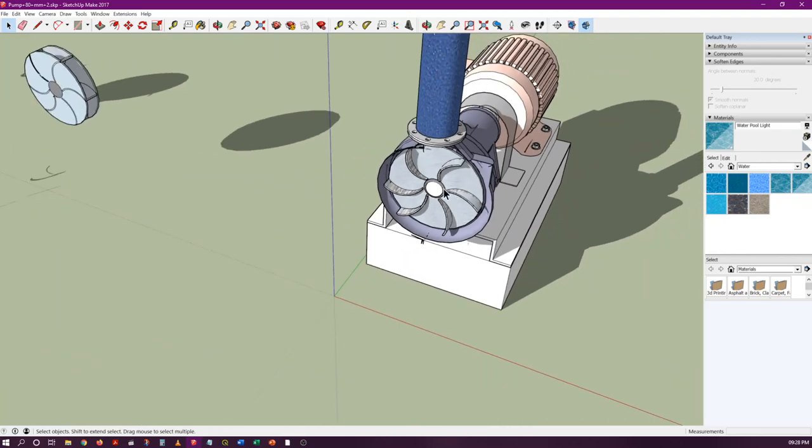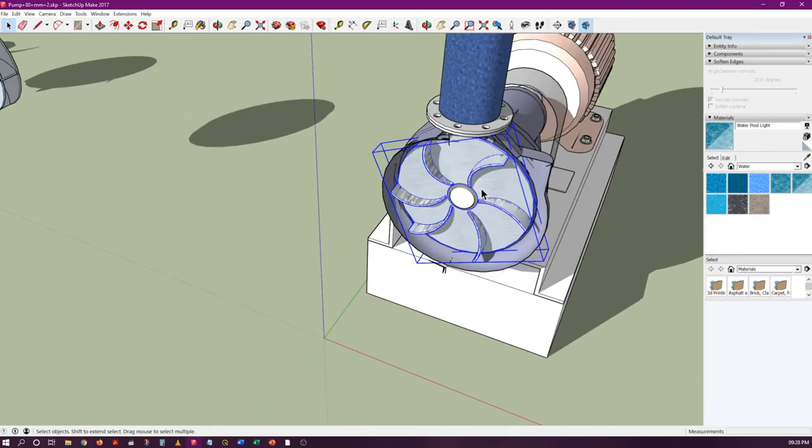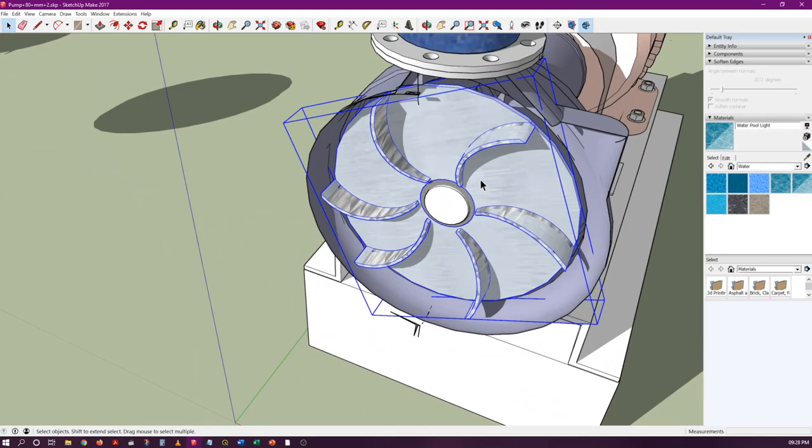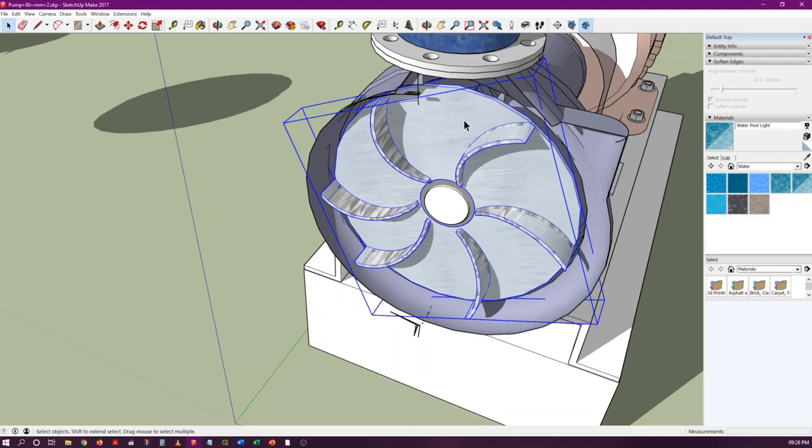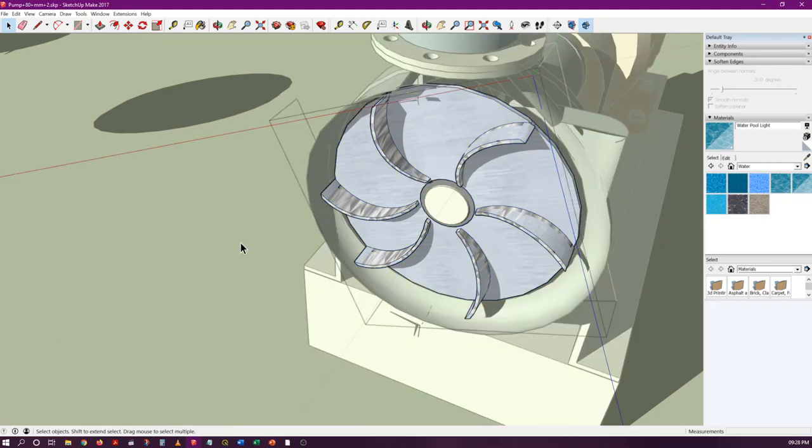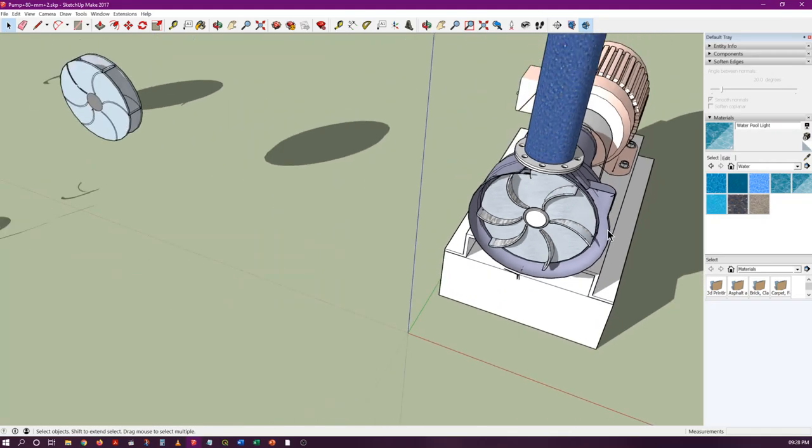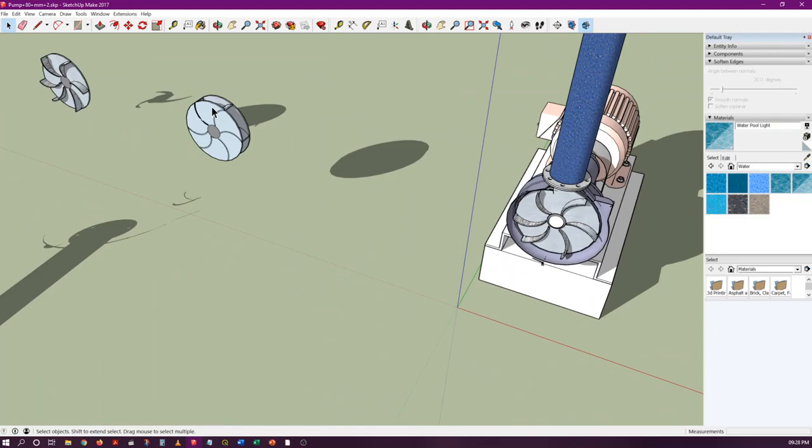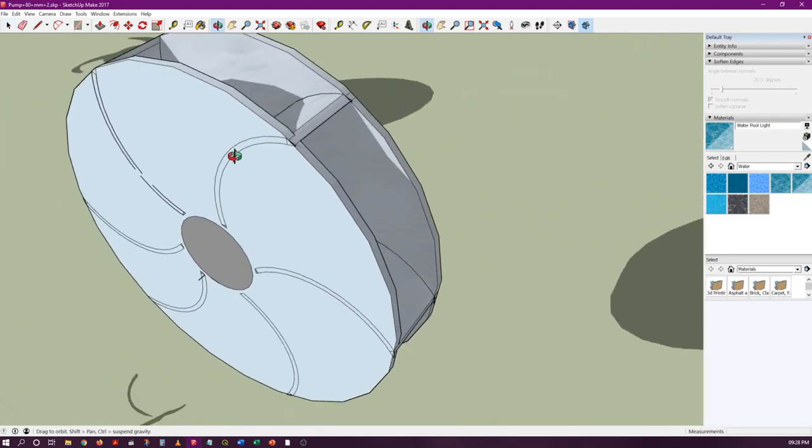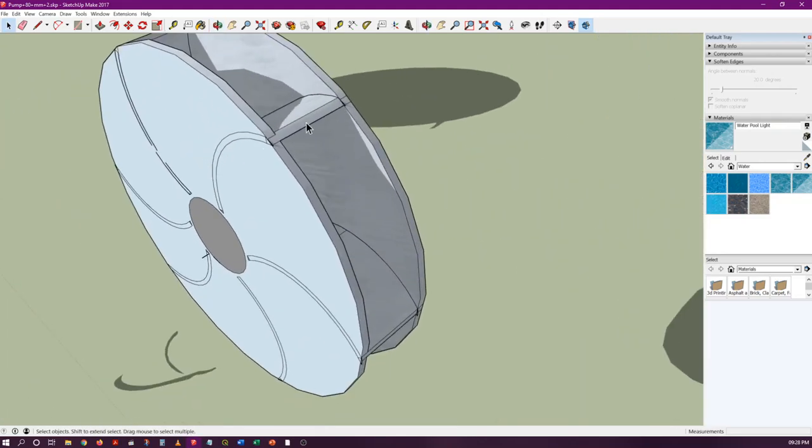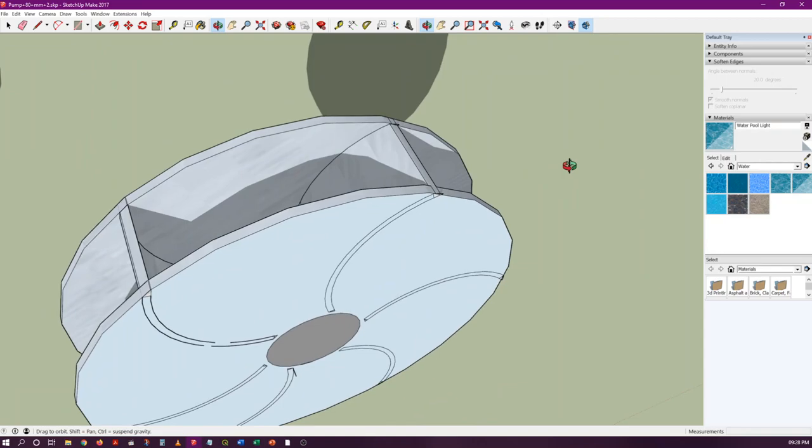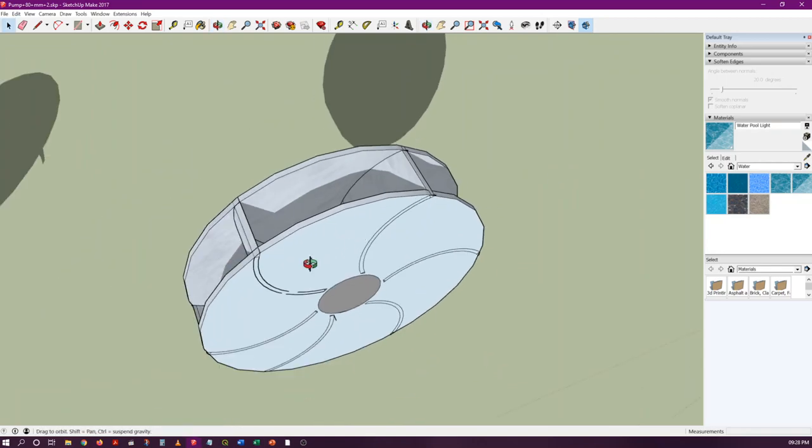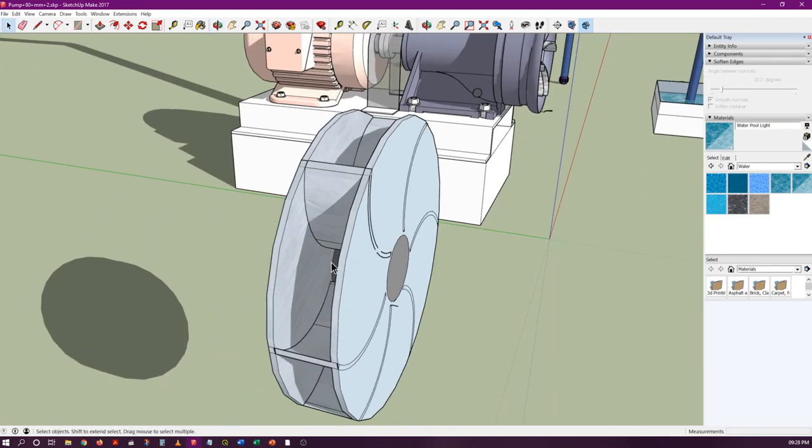There are different types of impellers. One is this one, called semi-open or semi-closed. The meaning is the same because one side is closed by this plate while the other side is open. There are other impellers where both sides are closed—the blades are sandwiched between two shrouds or plates.